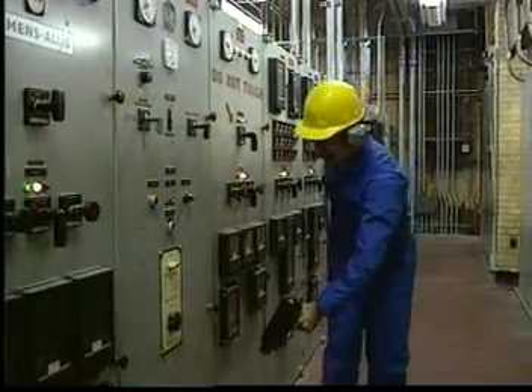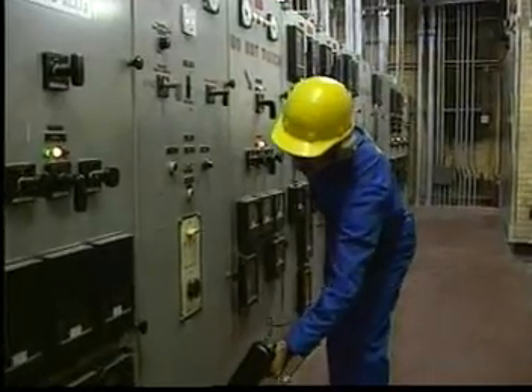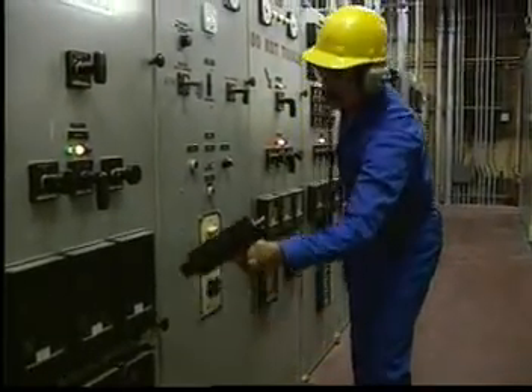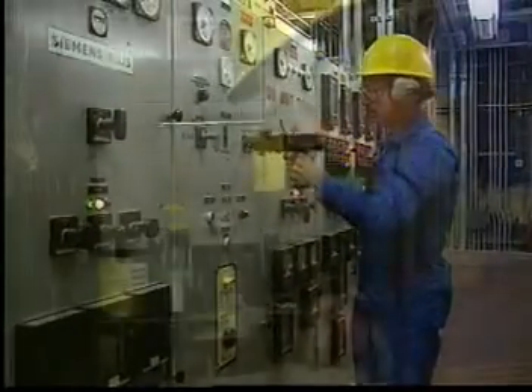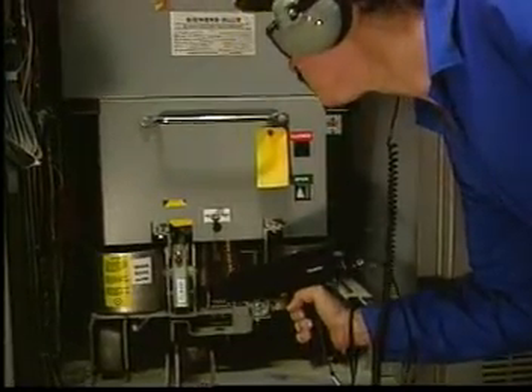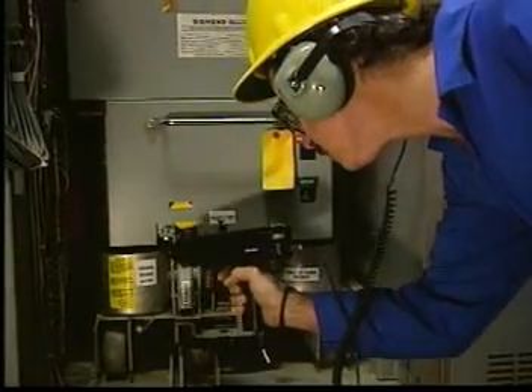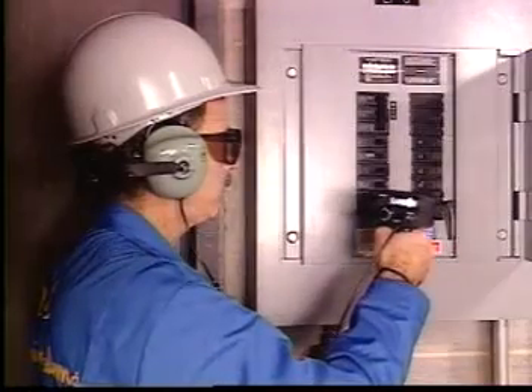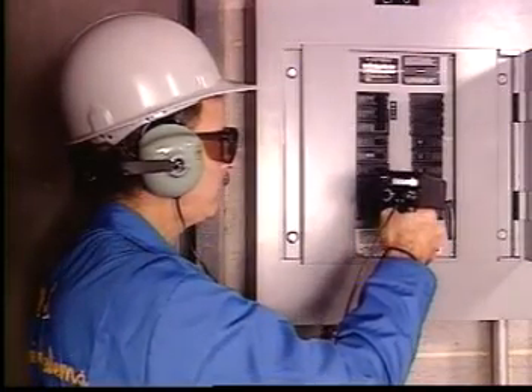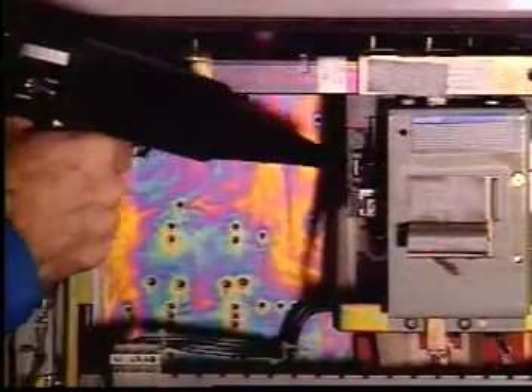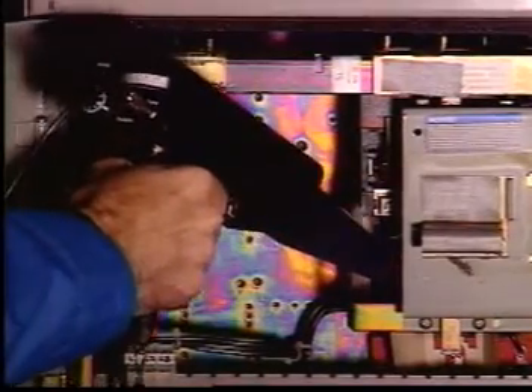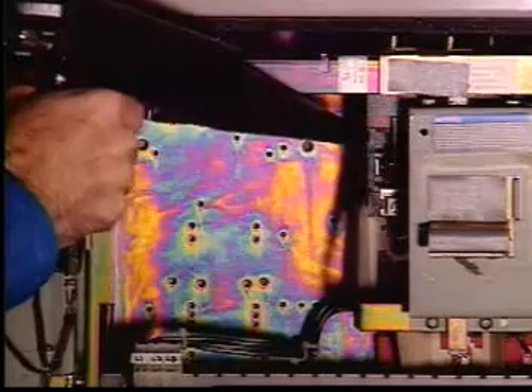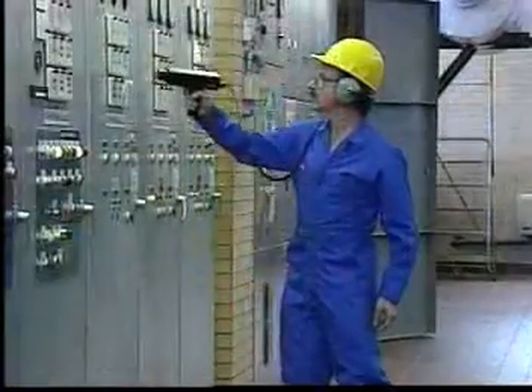Although the majority of the applications are for high voltage, there may be situations where it is appropriate to check low and medium voltage equipment, such as connectors, relays and contactors, splices, and occasionally circuit breakers where there may be loose wires or breakers. The ultraprobe may be used effectively in conjunction with other low voltage testing methods because of its ability to pinpoint the exact location of a problem.